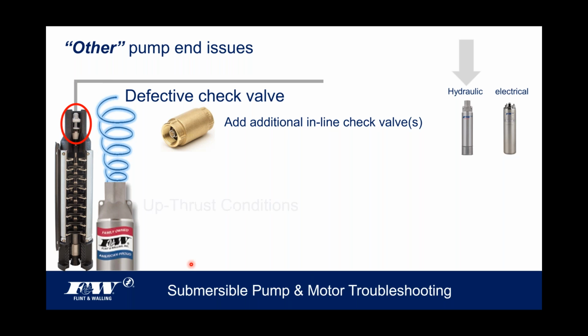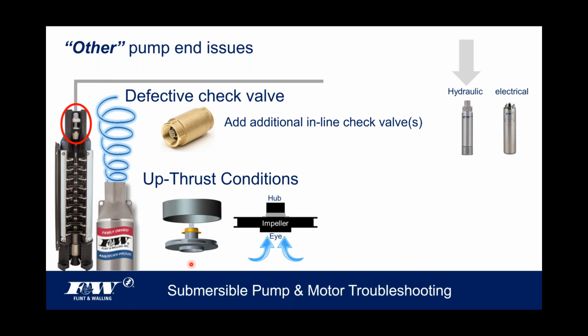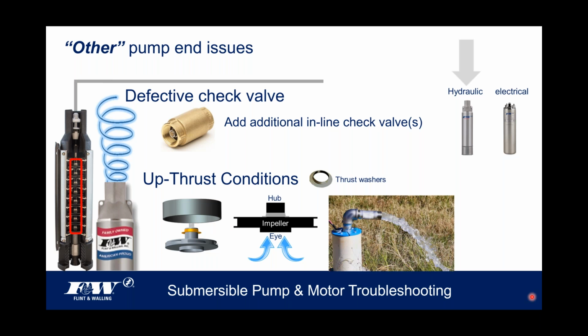Some other pump end issues are what's called upthrust conditions. All pumps are going to be subject to this. There's nobody that's immune from being in an upthrust condition. Again, if we look at this assembly down here, this impeller has an eye. It's on the bottom, that large opening. The hub sits up on top, and it's on that hub where we put a thrust washer. And if you look over on the left-hand side, that pump end, we happen to use stainless steel in our construction. You'll see that every one of those stages, every one of those impellers, will have a stainless steel thrust washer or thrust bearing around the hub of that impeller. And the reason behind this is right here, all right?